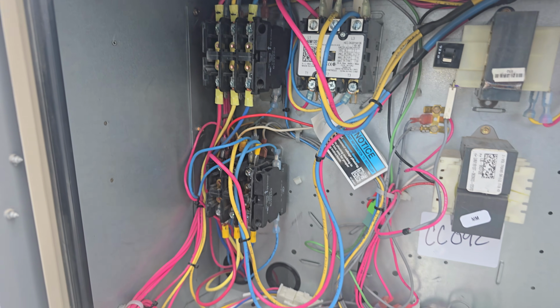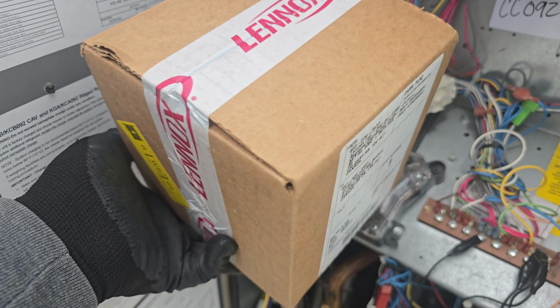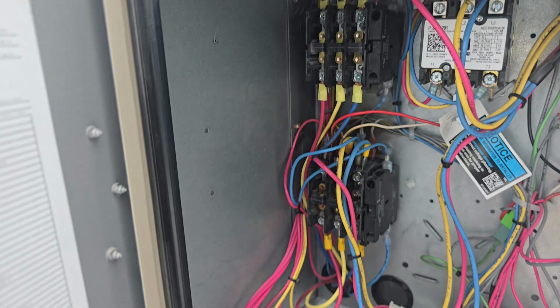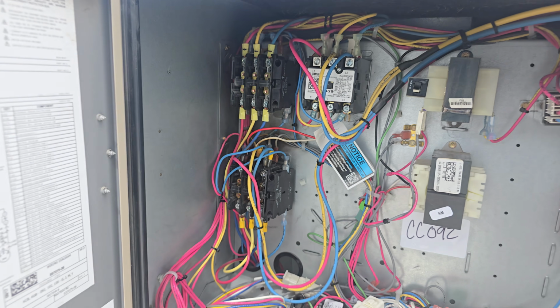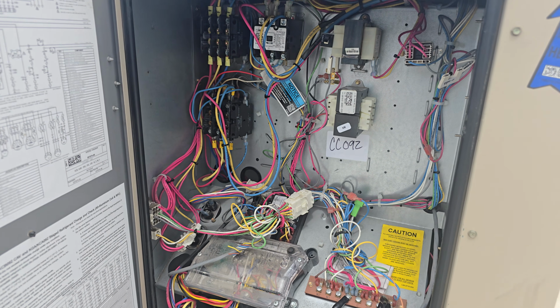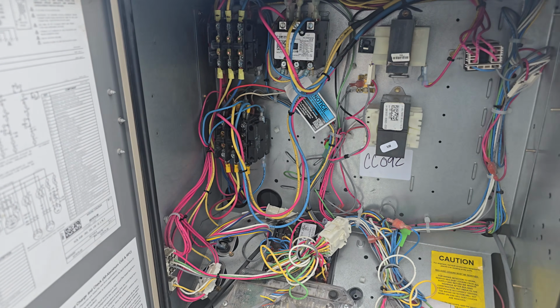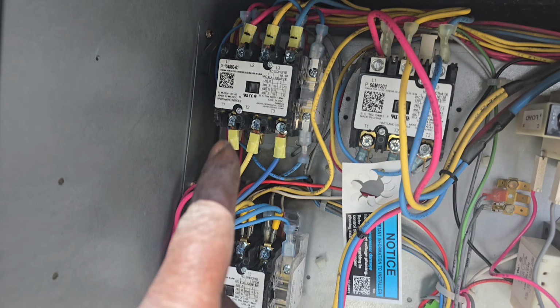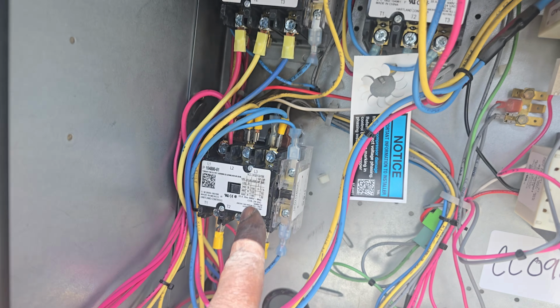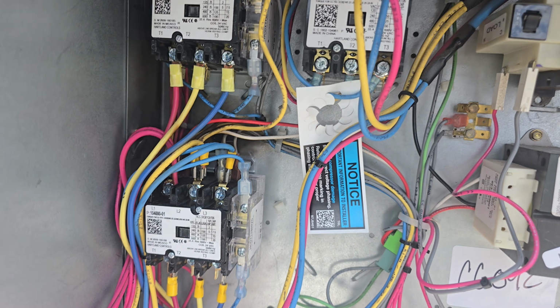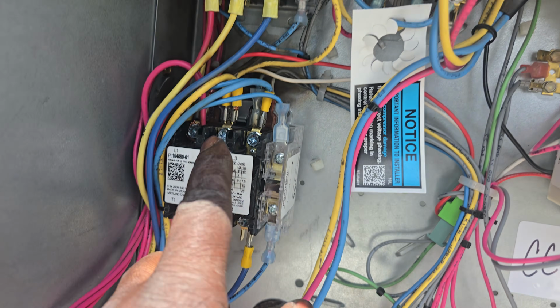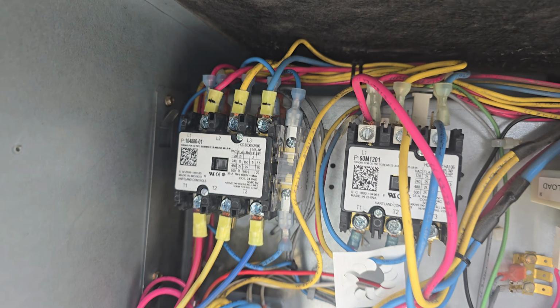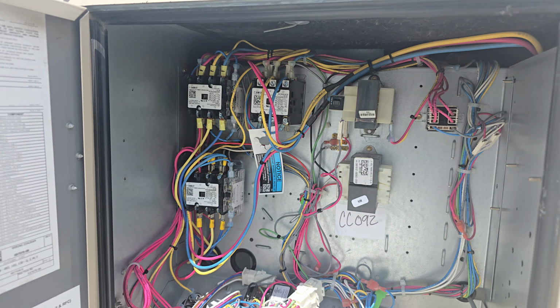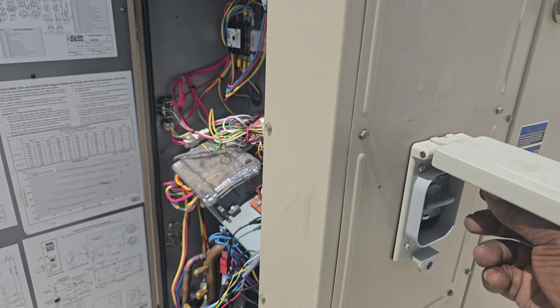Okay, so I have placed an order to replace this contactor, and here I have it in the box. So these two contactors came, I placed an order on them, and they are here now. So I'm going to put those in, and I'll keep you posted. Okay, so I have installed this contactor and the other contactor. So I have two contactors and also my relay. Please make sure all your wiring is properly intact. Cross-check it over and over again to make sure it is okay. Now that I have done that, I'm just going to turn on my unit and see.